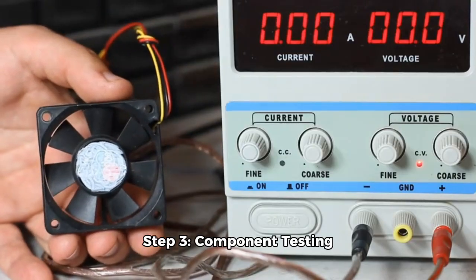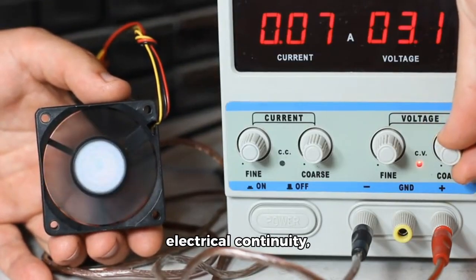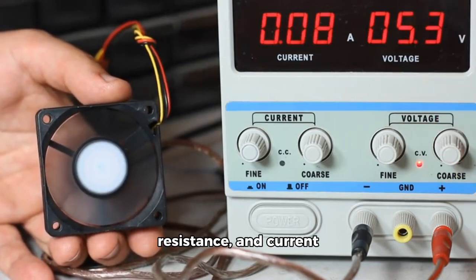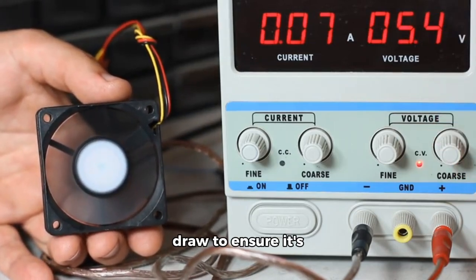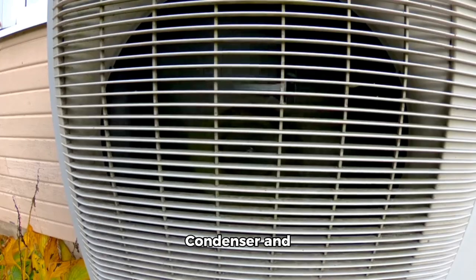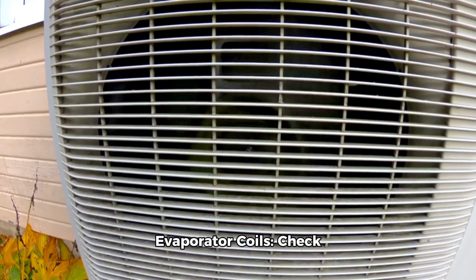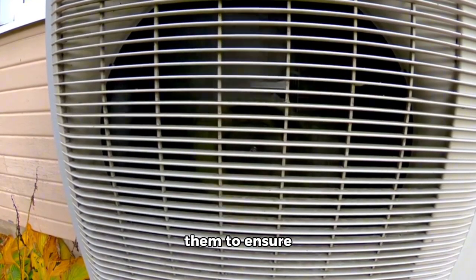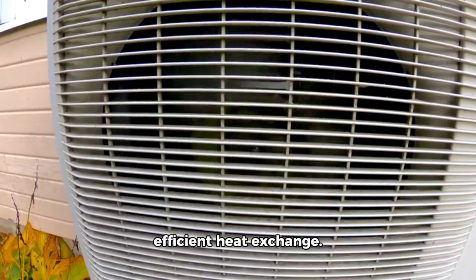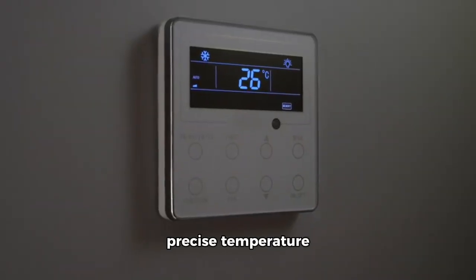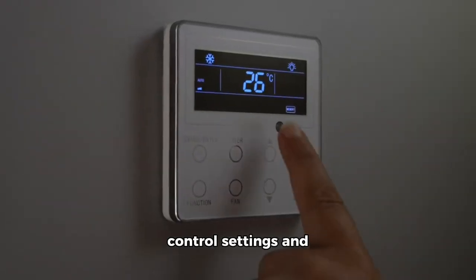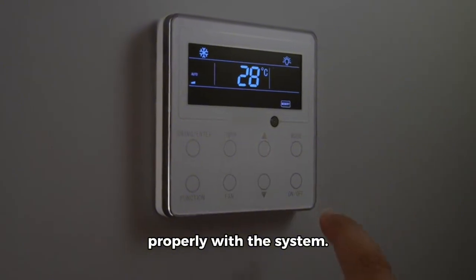Step 3. Component testing. Compressor. Test for electrical continuity, resistance, and current draw to ensure it's functioning correctly. Condenser and evaporator coils. Check for blockages and clean them to ensure efficient heat exchange. Thermostat. Test for precise temperature control settings and ensure it communicates properly with the system.